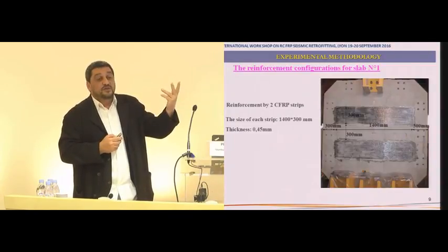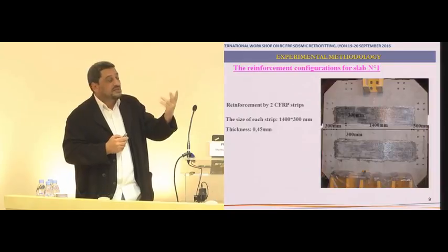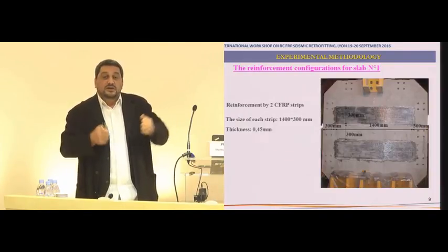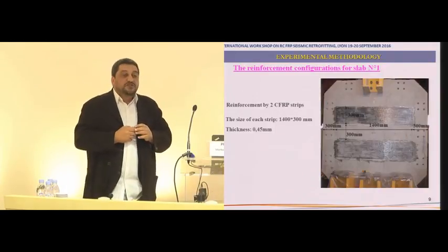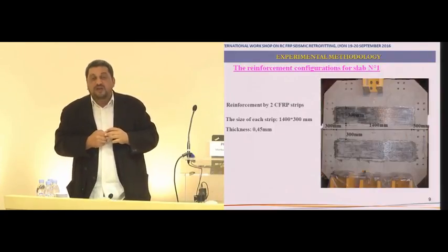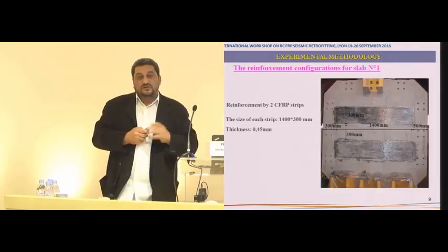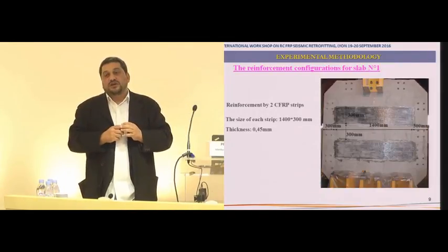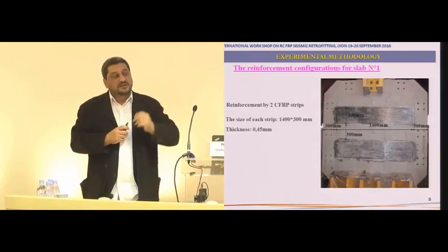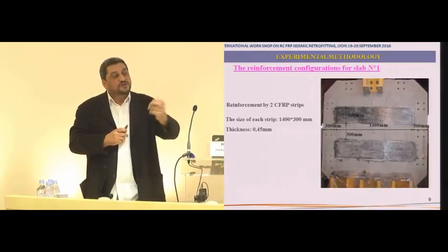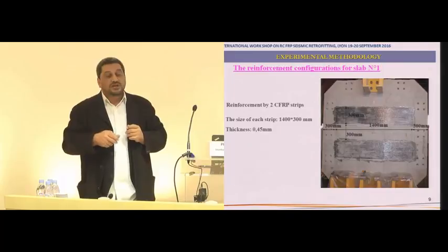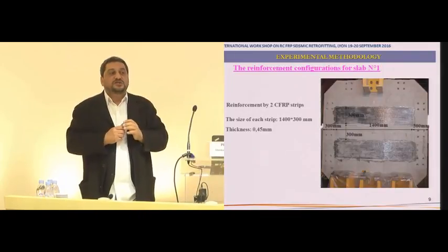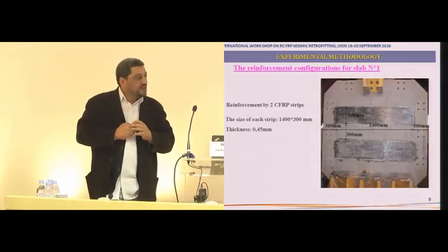For complicated cases, I mean by complicated case, the case where we have, for example, in-depth cracks. Why in-depth cracks? Because in cooling towers we have in-depth cracks, and we want to check if reinforcement with carbon layers can really enhance the rigidity and enhance the bearing capacity. What we show here is that we can enhance the bearing capacity, but not really the rigidity. Thank you.